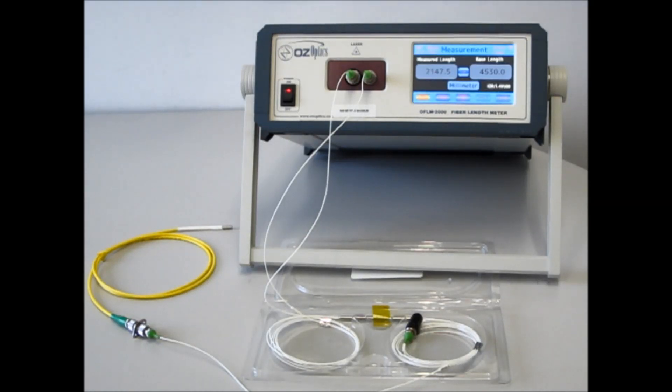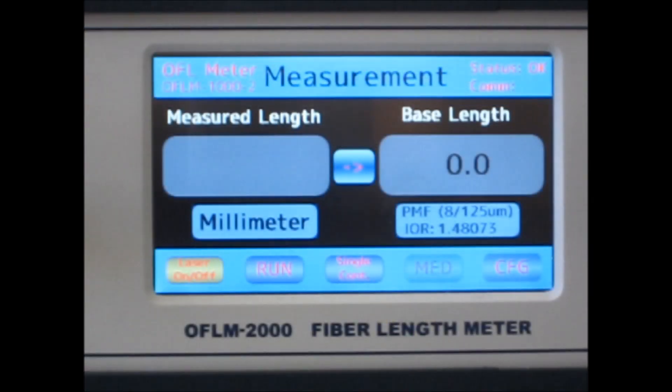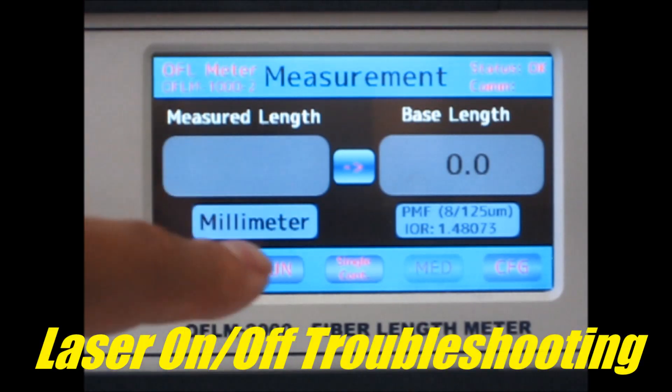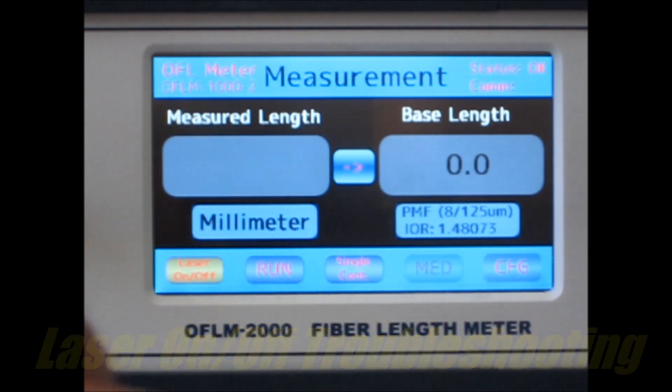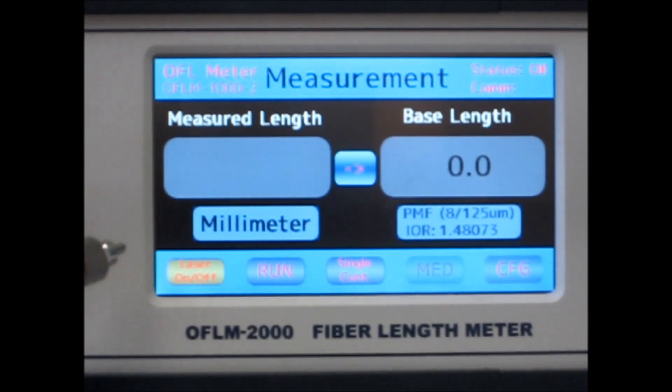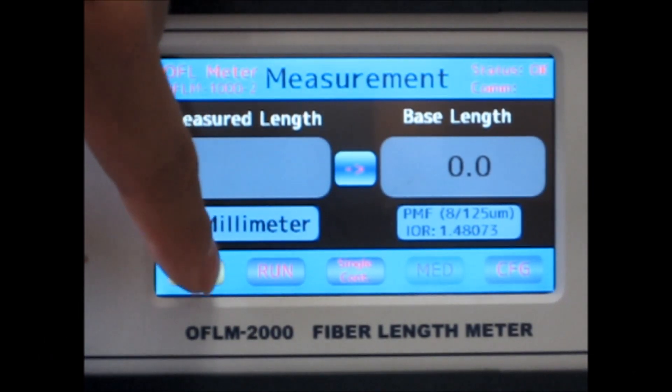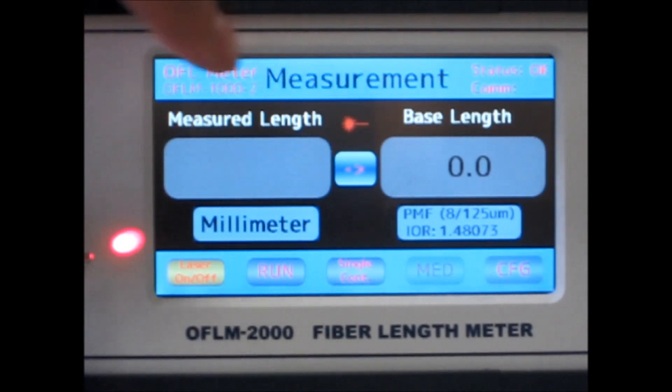So far we have avoided the leftmost button, the laser on-off button. This should only be used for troubleshooting purposes to see if there are any breaks in your fiber. It is not needed for measurements. When we push the laser on-off button, a continuous beam of red light is emitted and the laser warning symbol appears on the screen. When we push the button again, the beam and symbol turn off.